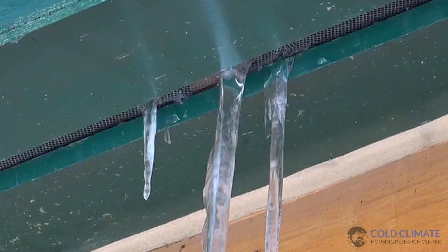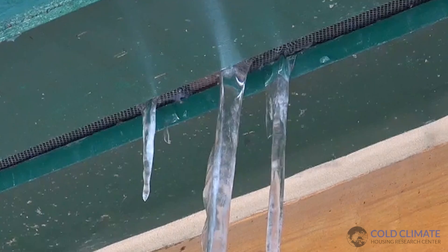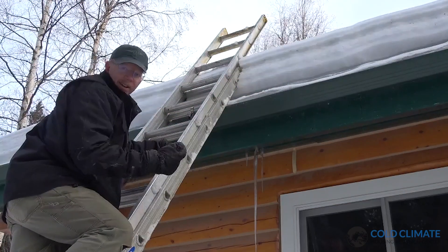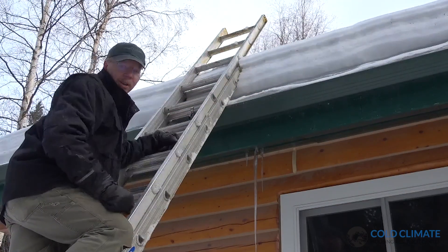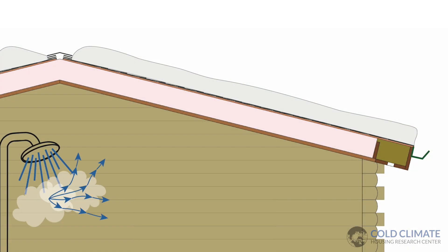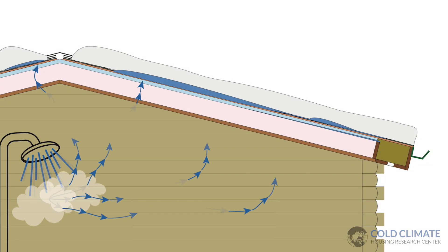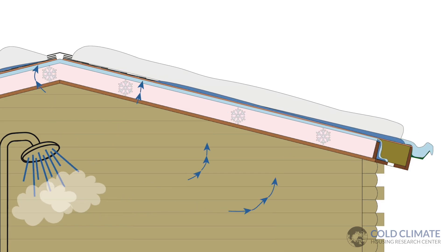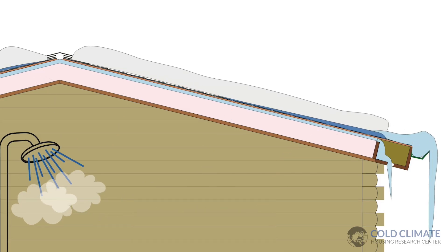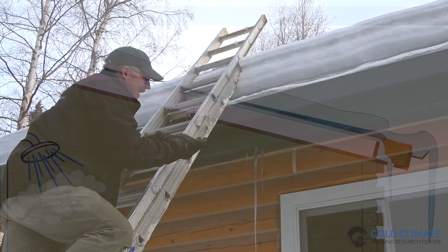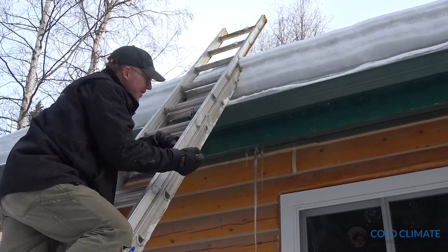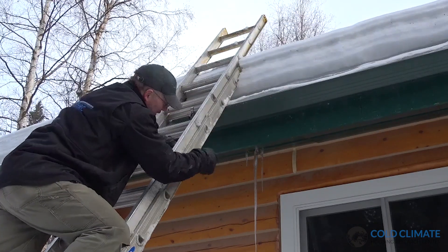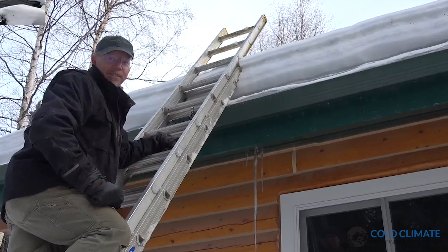My theory is that all winter long there's been air leakage up into this ceiling, and that air leakage has been transporting water vapor, which has then been condensing and freezing inside the rafter bays. Then we had an unseasonably warm day — it was 40 degrees — and all that ice that was building up inside the roof suddenly thawed, melted, and ran down over the wall and came out of this soffit vent.